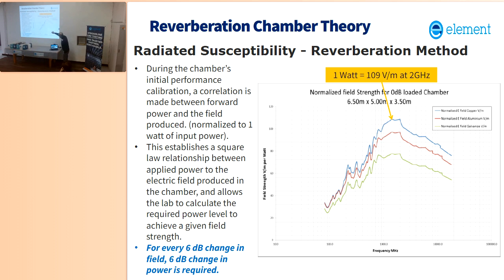Now this is a chamber that's calibrated down to 80 megahertz. Okay, so it's a relatively large chamber. But with the treatment on the walls, the copper on the walls, 1 watt of input power, and you get over 100 volts per meter at 2 gigahertz. Now, that's with no loading, right? Typical test units load down the chamber, so you might get 1 watt will give you 50 volts per meter because you've got loading in the chamber. But still, that's a lot of field for a fairly low power level, right?